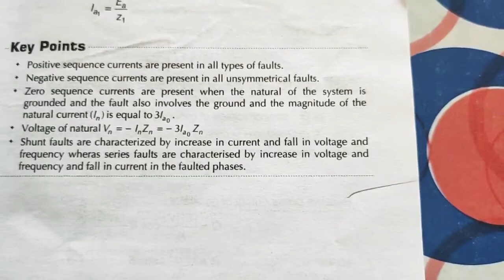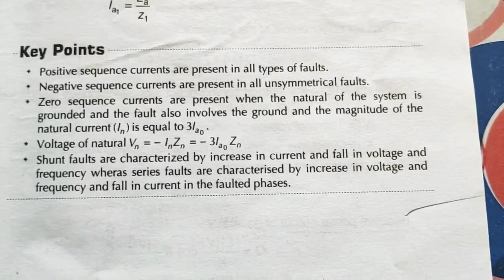Positive sequence currents are present in all types of faults. Negative sequence currents are present in all unsymmetrical faults. Zero sequence currents are present when the neutral of the system is grounded and the fault also involves the ground, and the magnitude of the neutral current IN is equal to 3 IA0. Then the voltage of neutral Vn is equal to minus IN Zn, that is equal to minus 3 IA0 Zn.